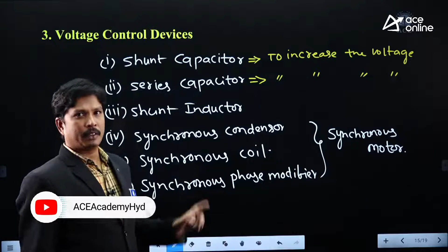Now I am giving some conclusions at this point. The shunt capacitor is always used to improve the voltage, to increase the voltage. So almost all the capacitors, whether connected in series or shunt, are going to increase the voltage. Series capacitor is also used to increase the voltage. But if you compare series capacitor and shunt capacitor, which device improves the voltage better? It will be the shunt capacitor. Definitely we will go for the shunt capacitor. Which connection is best for improving the power factor? Definitely the shunt capacitor. But which connection is better for stability improvement? It will be the series capacitor connection. It will be discussed in the subject whenever we enter into the actual subject. So everything will be discussed there. Clear up to here? I am giving just the conclusions here.